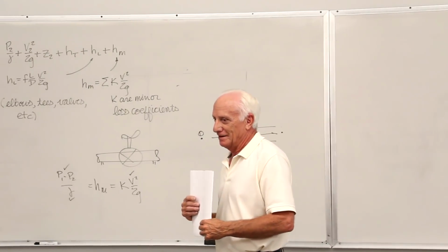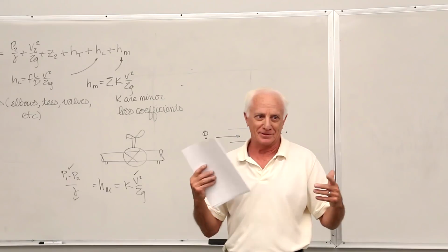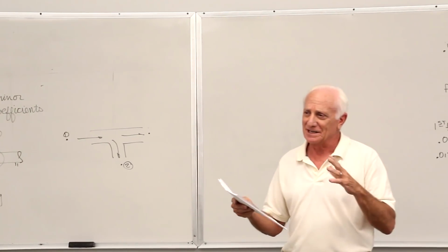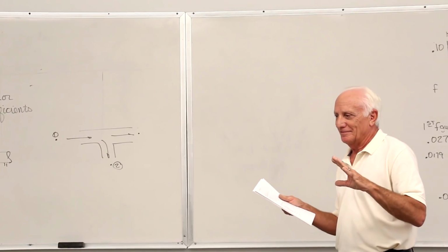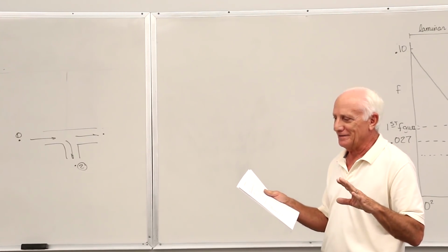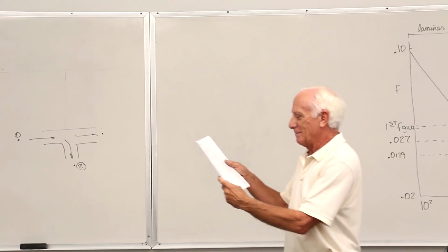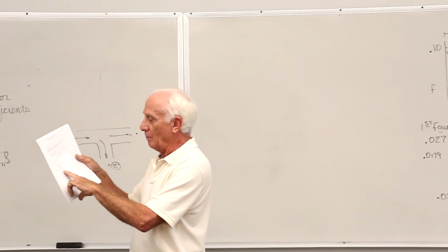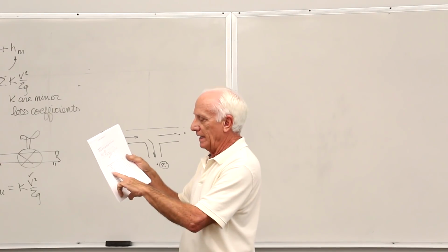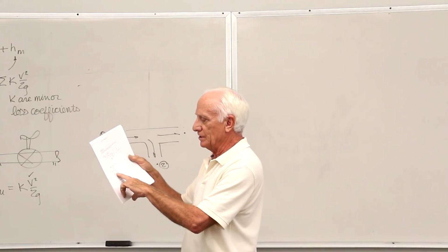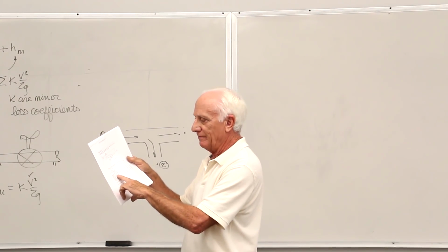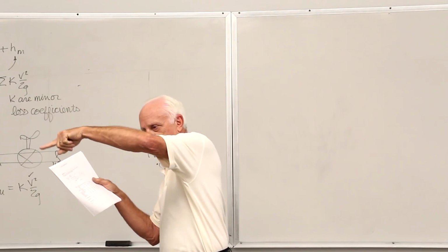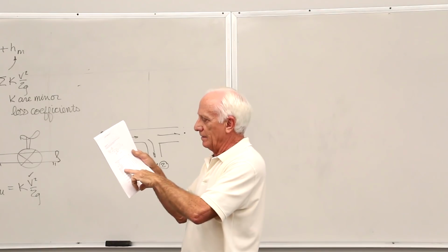They can vary dramatically, you know, plus or minus 30, 40, 50%, because everybody makes things a little bit differently. Valve manufacturers, filter manufacturers. Anyway, back to here. Globe valve. Is it fully open, half open, or 1/4 open? An angle valve, fully open. A swing check valve, fully open. A gate valve, fully open. A return bend where it makes a 180. The return bend is in there.